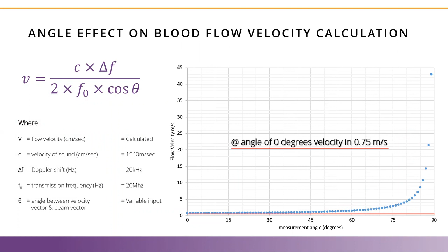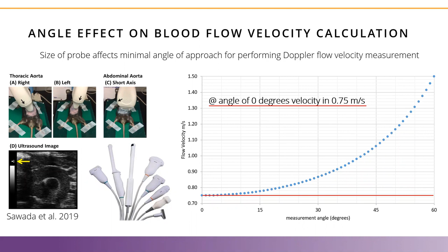Because in the previous image, you could clearly see that the angle effect would start skyrocketing approximately past 60 degrees. But looking at this graph, you can clearly see that from 0 to 60, there is already a steep increase in the flow velocity calculations. From 0 to 60 degrees, there is basically a twofold increase in the calculated flow velocity. To further highlight this, we're taking this graph in two sections, where you can see the increase in flow velocity from 0 to 20 degrees and the increase in flow velocity from 40 to 60 degrees, which is often seen as the operating range when using an echocardiograph system.